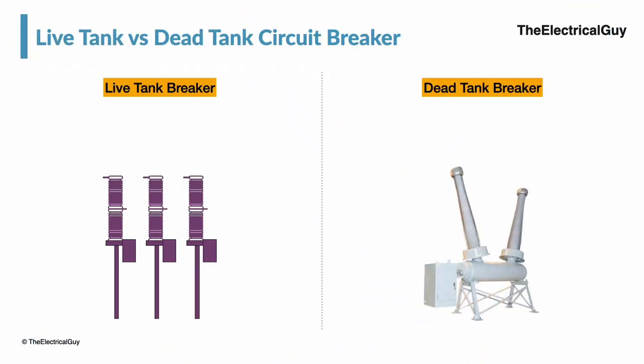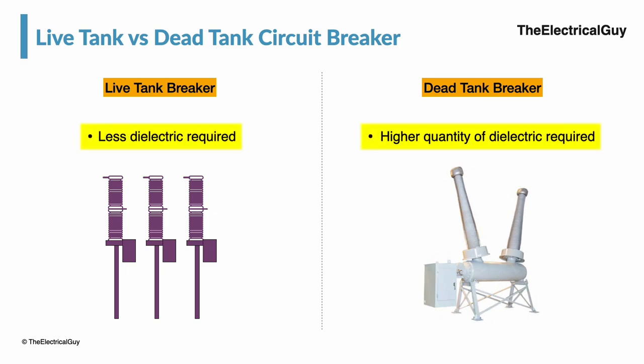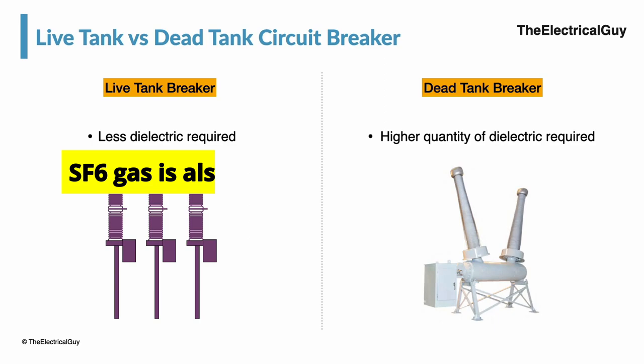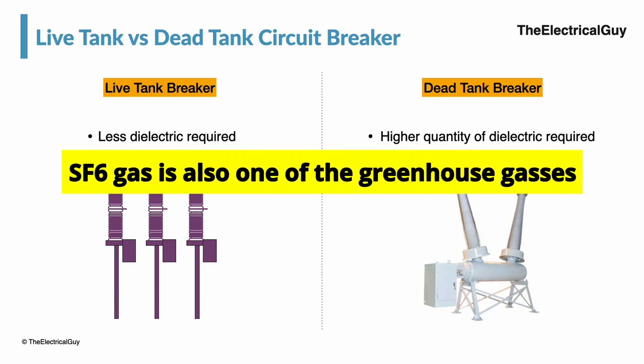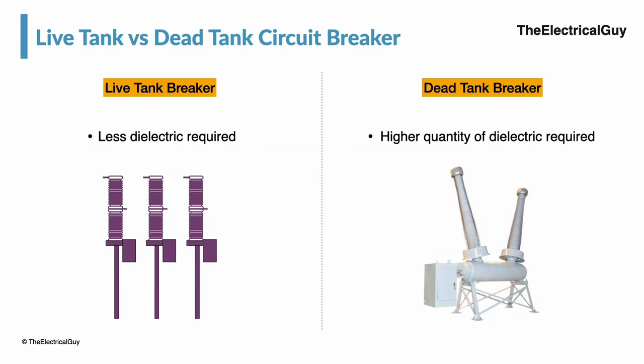It is important to note that in a dead tank circuit breaker, the quantity of dielectric required is more than in the live tank breaker. If SF6 gas is used as the dielectric medium, a dead tank breaker would need more gas than the live tank breaker. Since SF6 gas is also a greenhouse gas, in case of leakage, a dead tank circuit breaker would cause more damage to the environment than the live tank breaker.